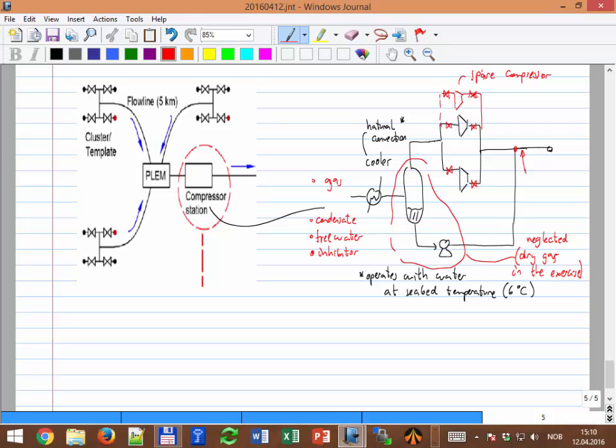And what I'm going to do is to put it in operation. This is normally closed, okay, and these two are open. If I have problems with one of them, I just close that valve and I open this one, and no problem. I can maintain production like if nothing happened. Then I go, I make maintenance, I pull out.